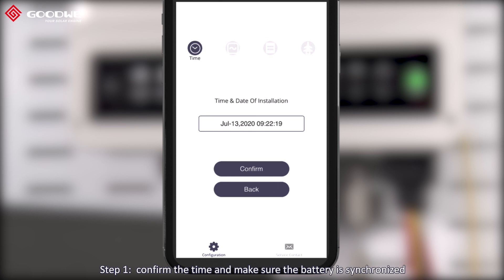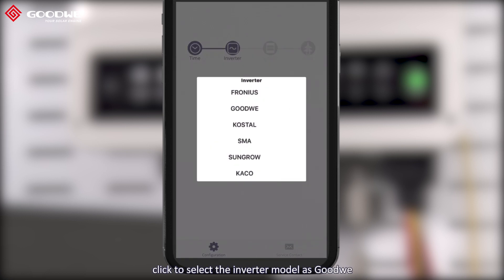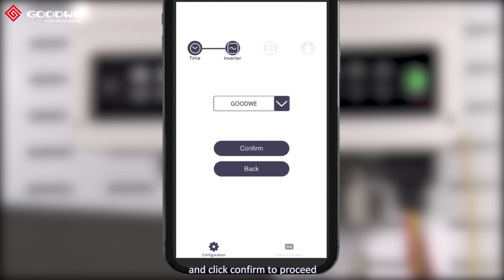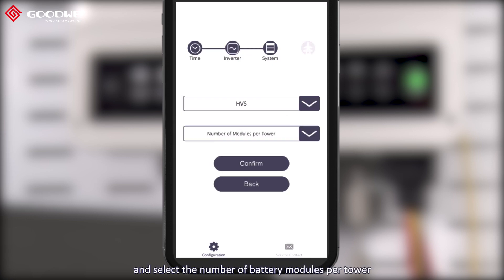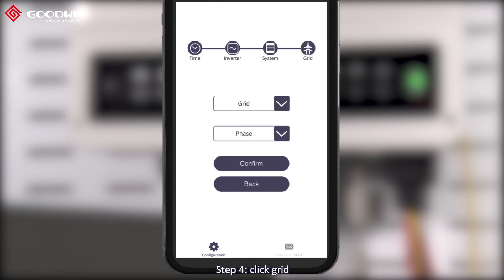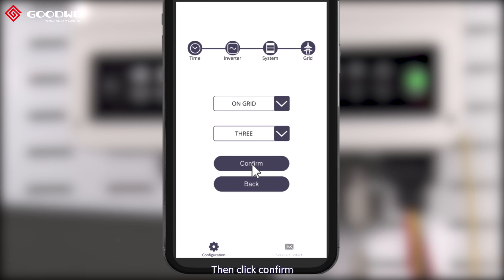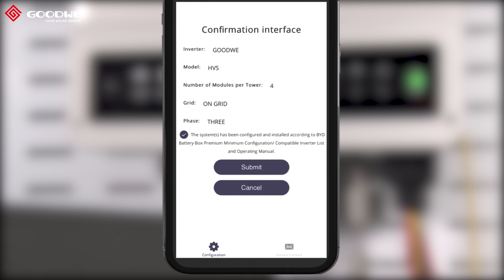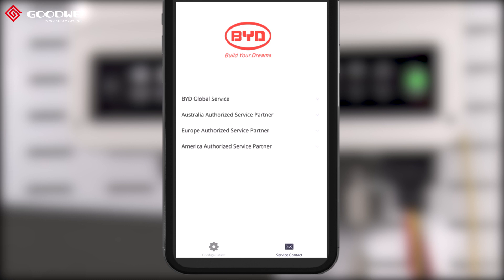Step one: confirm the time and make sure the battery is synchronized with the current time. Step two: select the inverter model as GoodWe and click confirm. Step three: select the battery model name and the number of battery modules per tower, then click confirm. Step four: click grid to choose on-grid, then click phase to choose three-phase, click confirm, and check the box. Submit the configuration for the battery and click complete. The configuration on the HVS battery is now finished.